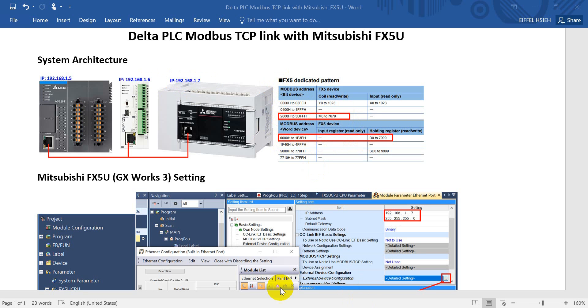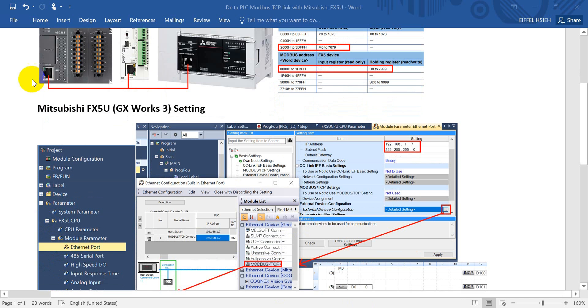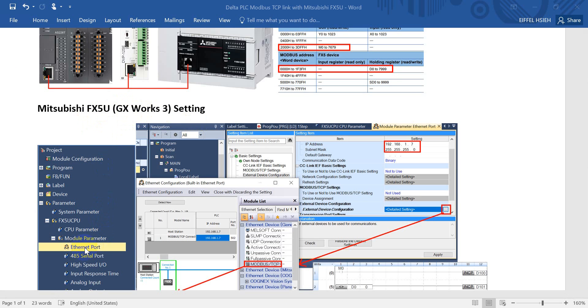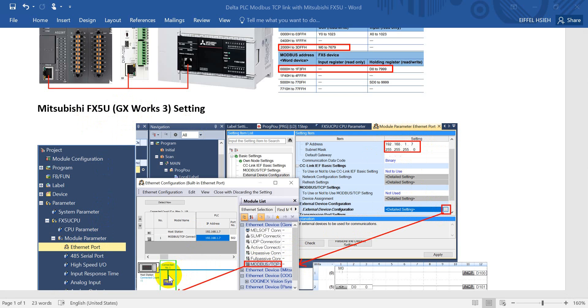Now we move to the Mitsubishi FX5U GX Works 3 settings. First we double-click the Ethernet port and then define IP address 2.1.7. Then go to the external device configuration. Select the Modbus TCP and add it to the network of FX5U.